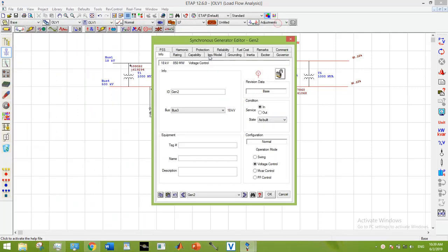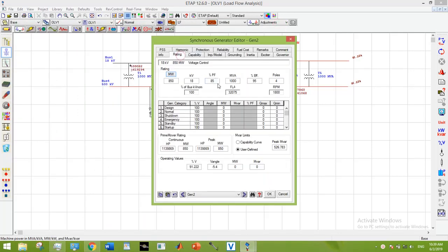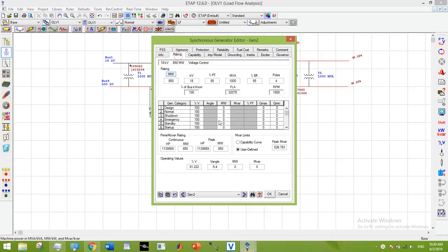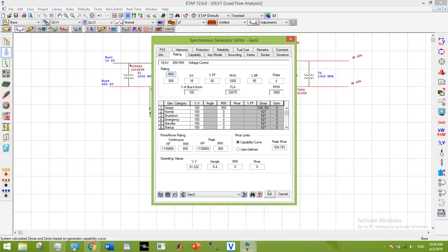And here in the rating tab, I am going to enter my active power and for Mvar limits, I could either go for user defined or I could go with capability curve. Right now, I am going with this capability curve. So, it will make its calculations itself.